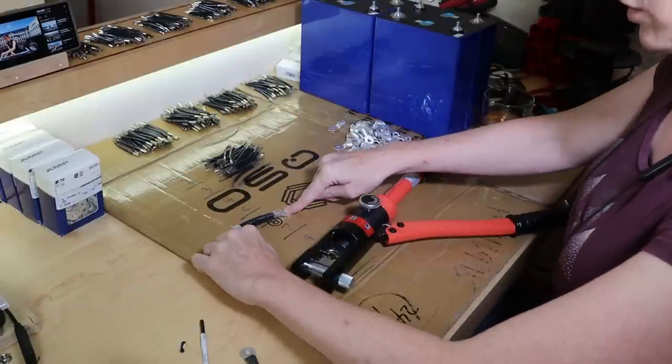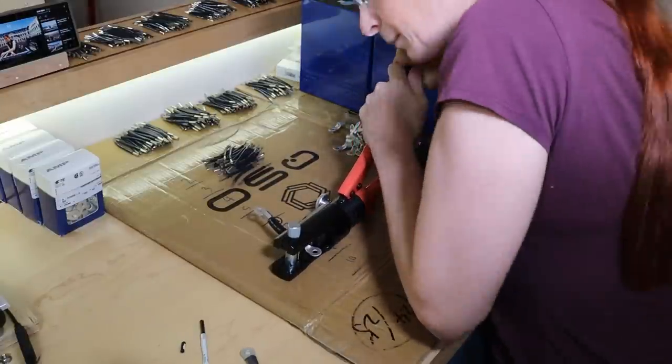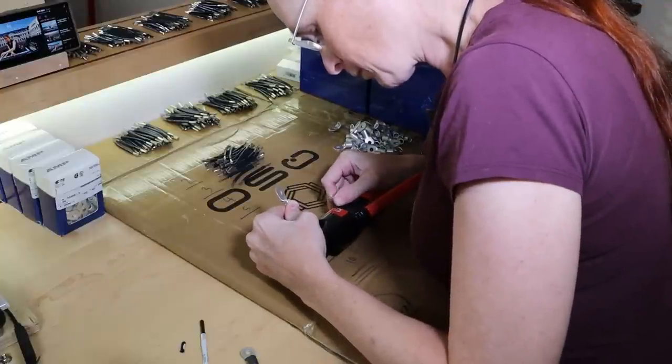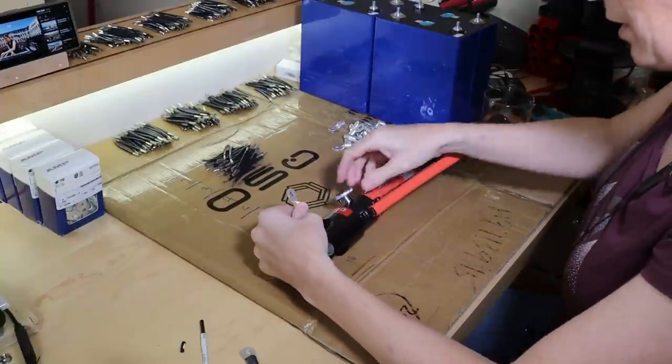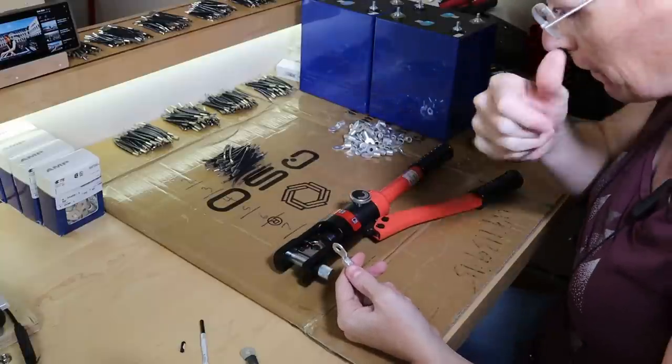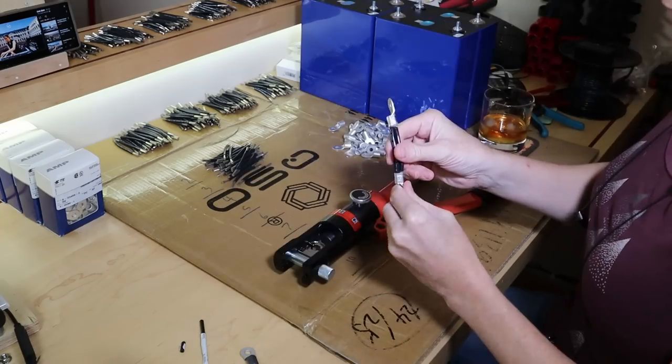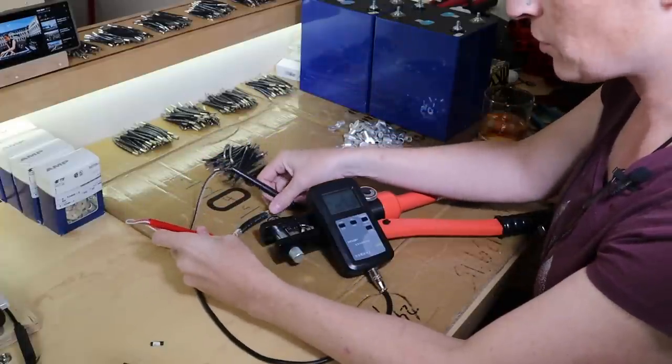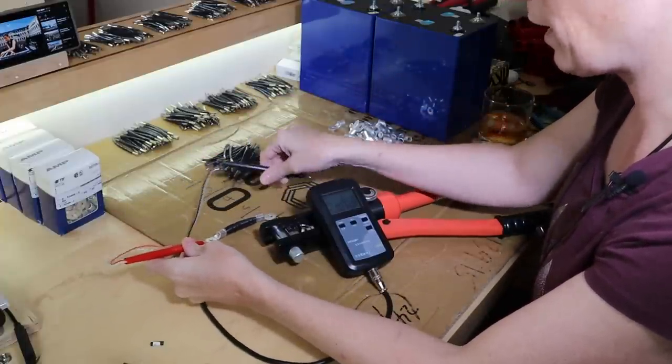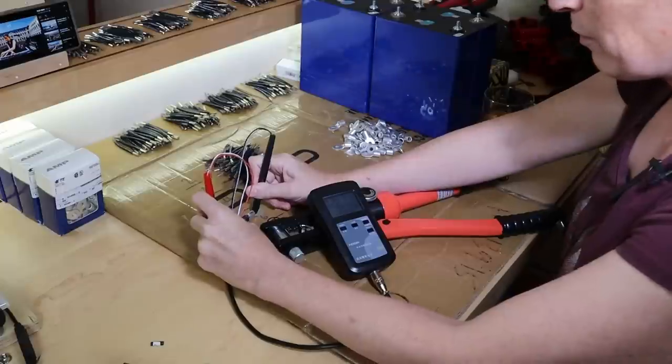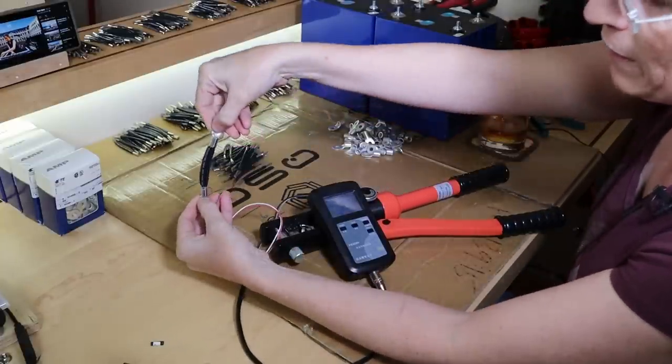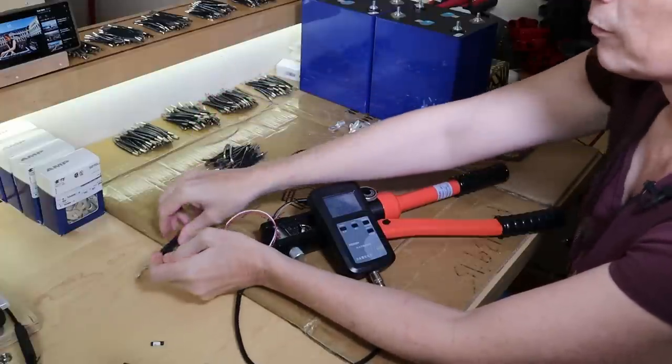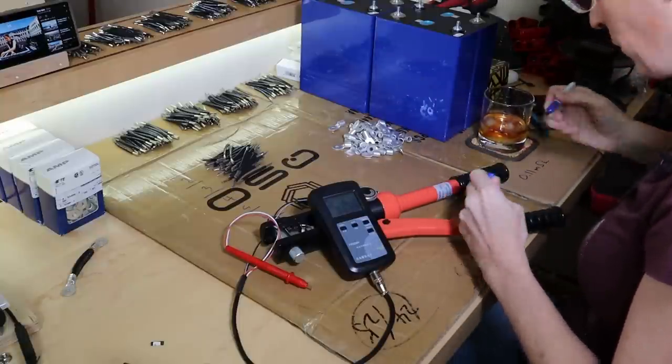There we go. I'm doing my best to make sure that these two stay level. It seems to be about level. All right, what I'm trying to do here is I don't want to just turn it off because then this piston goes all the way back. And that means a lot more pumping before it closes up enough to have bite. But there! The first of 90. Hopefully you can see that. For consistency I'm always going to measure the end of the ring terminal to the end of the ring terminal. 0.11 milliohms. How much different is it if I check at the base? Huh! 0.07 milliohms. Gives you an idea of just how quickly resistance goes up. From in here, 0.07 to out here, 0.11.